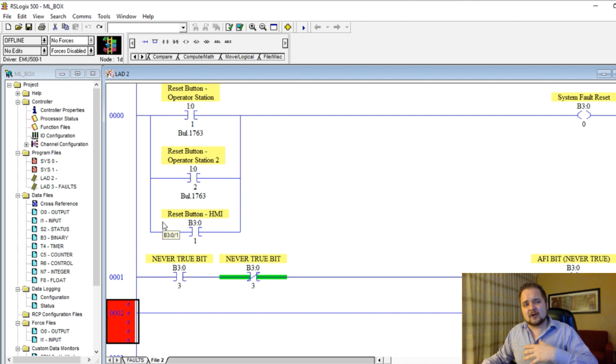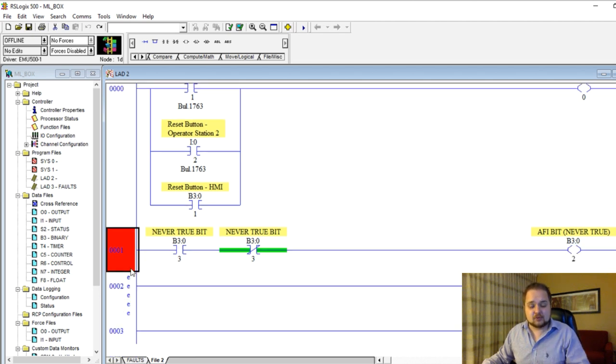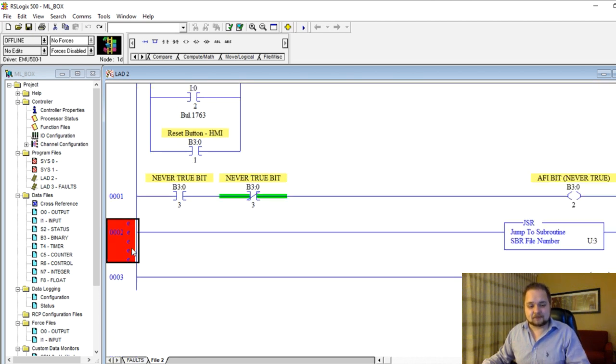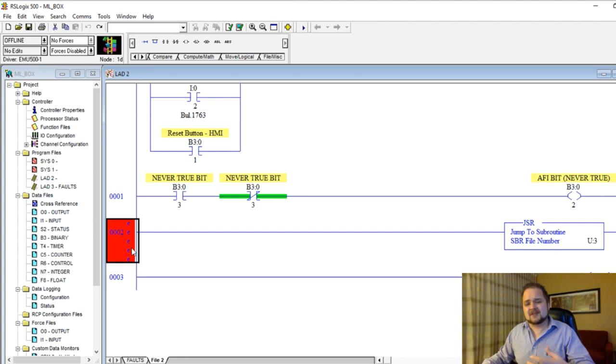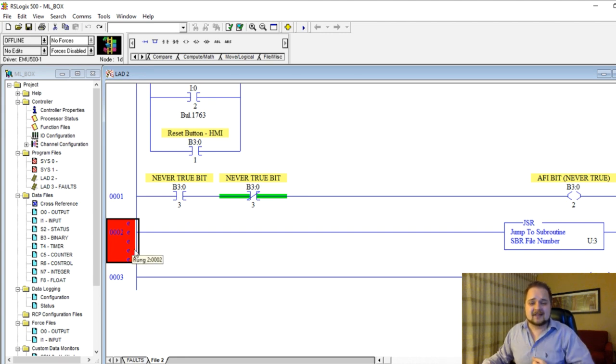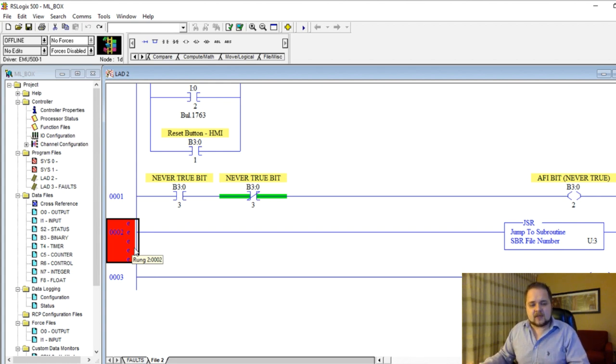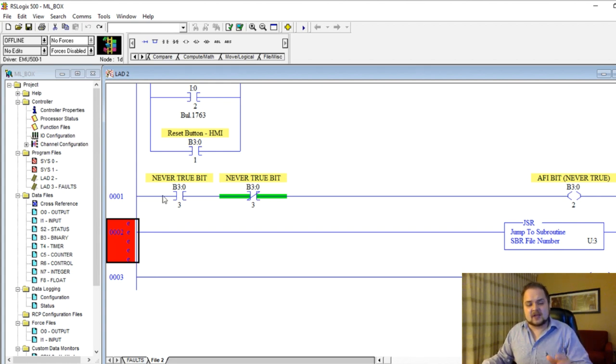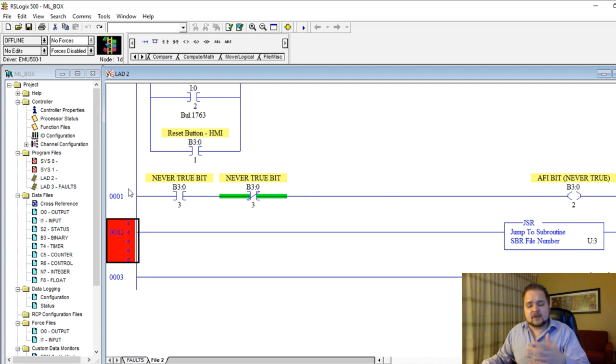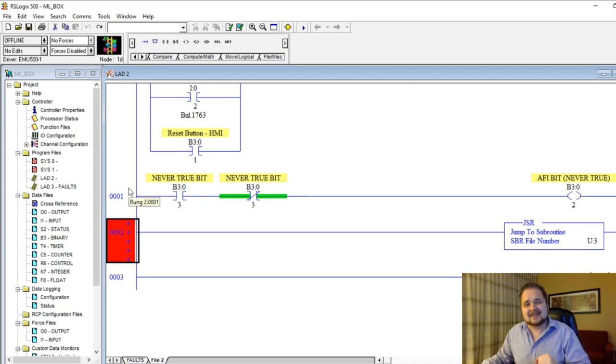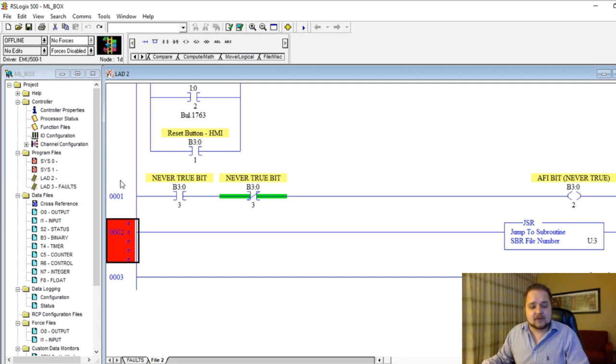Now depending on the different cards, you might be able to translate that locally on the card, but the easier way is to stay with the default setting on the card and translate that in software. That way somebody who's replacing the card physically doesn't have to necessarily go back and check the settings that everything is okay. Or if somebody moves the signal, it's just very easy to keep the same settings all across the board and then redirect to an instruction.